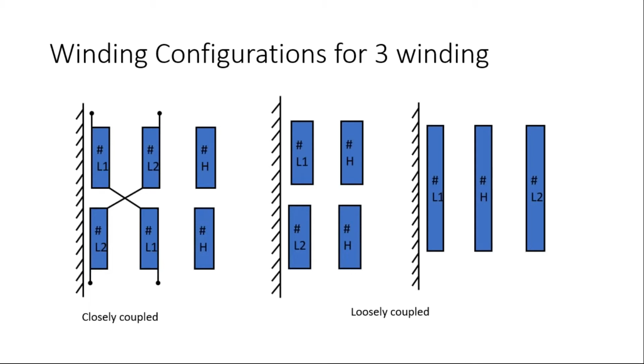So when it comes to winding configuration, when we have 3 winding transformers, which means we have 2 secondary windings, the coupling factor comes into play. So we have 2 different couplings, closely coupled and loosely coupled. There is one more coupling, partially coupled, which is not used very often because of strong axial forces.